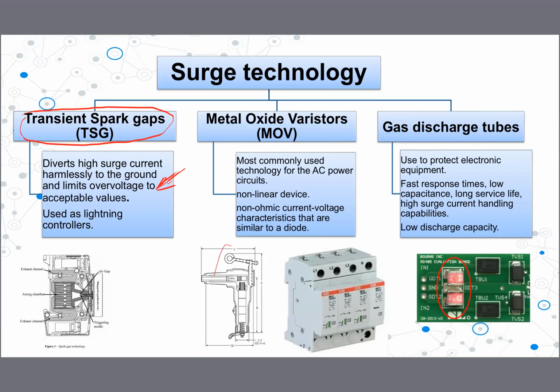It's like this. Then the third type, the gas discharge tube. Gas discharge tubes we mostly use in electronic circuits, right? Within the circuit, you can see this gas discharge type surge protection device, used to protect the electronic equipment. Mostly we use this gas discharge tube, right? It has a fast response time, low capacitance, and longer lifetime also. It can handle high surges as well, right? But it has a very low discharge capacity. So these are the three different technologies we use nowadays for surge protection as SPDs, right?